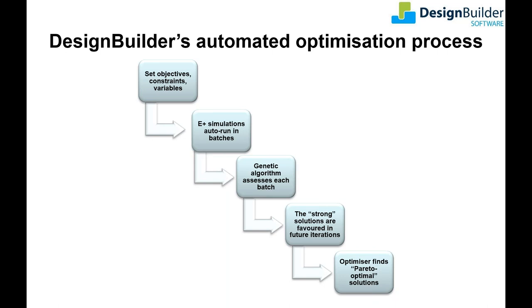Once the optimization starts, it generates input files for EnergyPlus simulations which are run in batches. The genetic algorithm assesses each batch of results to find the strongest solutions, then uses that information to generate future simulation input files specifying the design variable characteristics most likely to generate the strongest results. The whole process is automated and repeated until the optimizer has found all the likely strong solutions in the whole design space. Once the optimizer stops finding optimum solutions, the process stops.